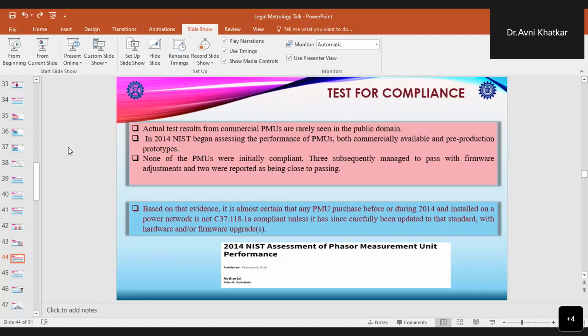So based on this evidence, it is almost certain that any PMU which was purchased before or during 2014 and installed on the power network is not compliant as per the IEEE standard, unless it has been carefully updated to that standard with hardware or firmware upgrades. This information is available in the public domain in the form of the report published by NIST, and it provides a number of insights into PMU behavior. However, it is restricted in showing generalized results in order to maintain manufacturer confidentiality.